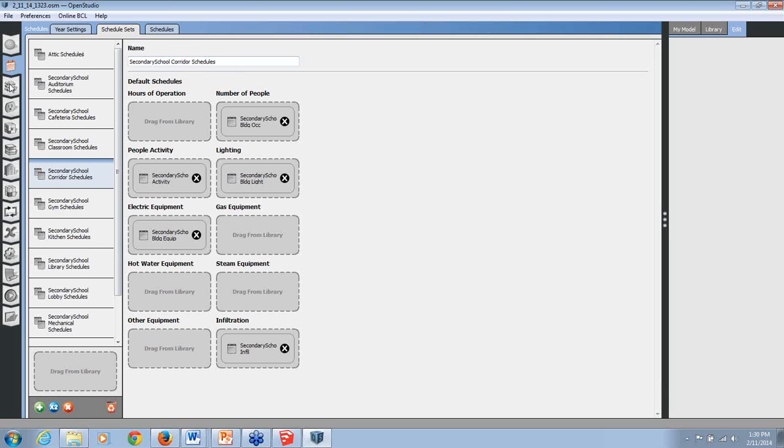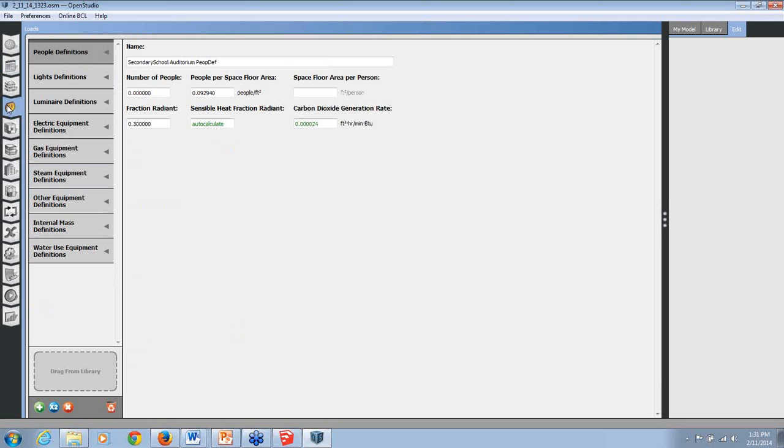Okay, so moving on again, just briefly showing how Energy Plus handles these objects, because there are a number of differences between OpenStudio and Energy Plus. One is in loads. You may be familiar in Energy Plus with how we describe lights, people, equipment, gas equipment, other equipment, steam equipment, and so forth, as simple IDF objects. In OpenStudio, we do it a bit differently. We describe a definition.